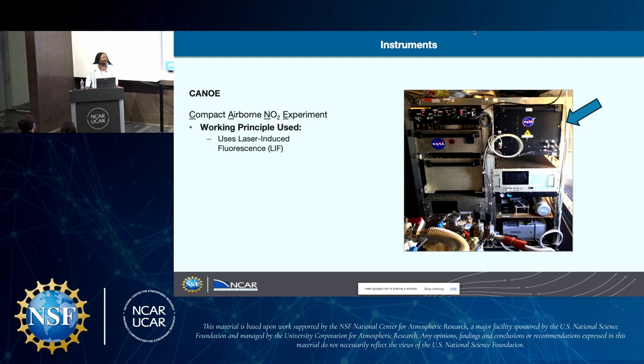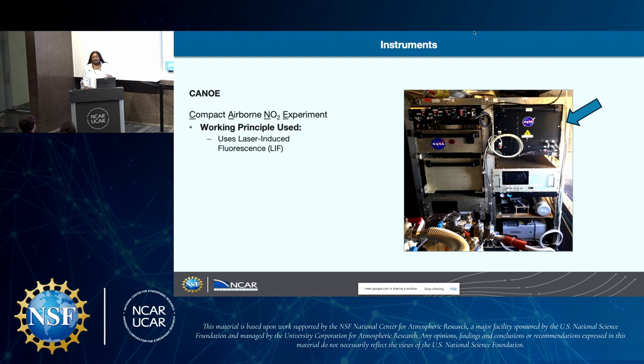CANOE's working principle is that it uses laser-induced fluorescence, or LIF. LIF is a method that uses a laser to excite the NO2 molecules. Those excited NO2 molecules will then emit light, and when they relax to their ground state, they are detected with a photomultiplier, which we also call a PMT.